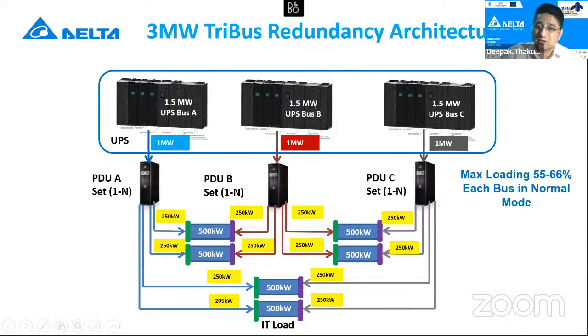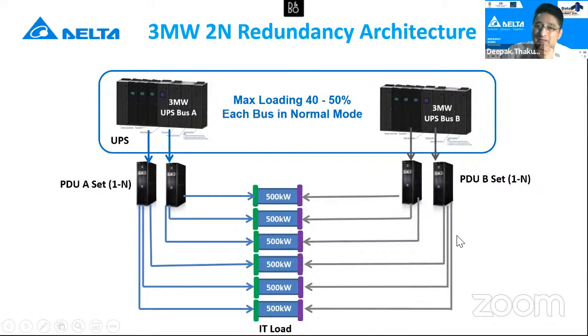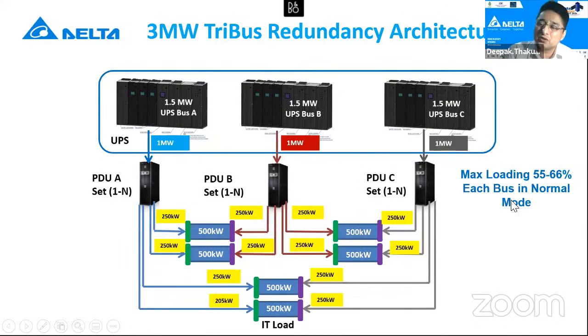And the previous architecture also, you were giving the 2N architecture. There is nothing much. The only thing is that you are loading this maximum to 40 to 50% on each bus. And that's the capacity. You cannot exceed that. Out here, you are actually optimizing your CapEx investment utilization by loading maximum to 55 to 66%, depending upon the design loads which you cater to. So you are actually bringing your OPEX also better, because at that load, the efficiencies go better in these equipments. And you're actually utilizing the CapEx invested for those equipments to deliver the kind of output, which is a 2N architecture output.